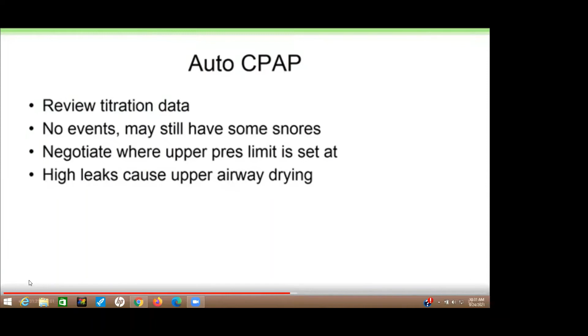If the patient is ordered on auto CPAP, you should make sure that the minimum pressure is adequate for comfort. Not a good idea always, just sometimes a physician will just set a wide open pressure, and that's okay if you have no idea, if you have no titration data to go on, just to see what the download will show and then tweak it later on. But typically a minimum pressure is set at 5 to 7 and a max of 20.